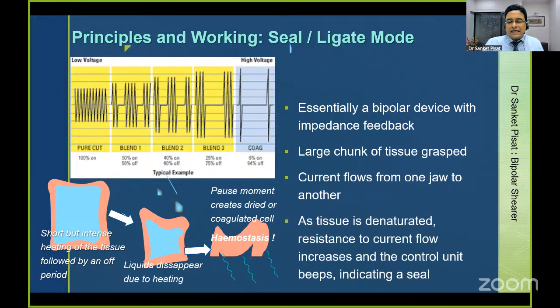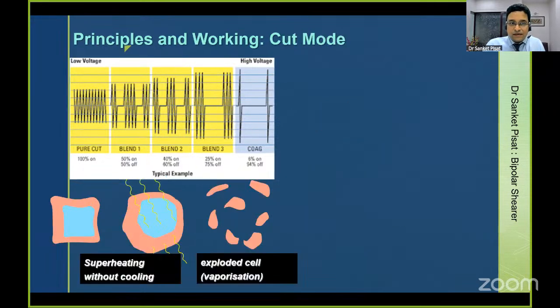As the tissue starts getting denatured by the flow of current, obviously the resistance to flow between the two points will keep on increasing. When the resistance reaches a critical preset point, which has been fed into the machine, the control unit beeps and indicates that there is a seal, meaning that you do not need to provide any more current in order to coagulate this tissue. So this is how the machine works in ligate mode, and essentially this is the same method of working of a LigaSure or any other advanced hemostasis device as well.